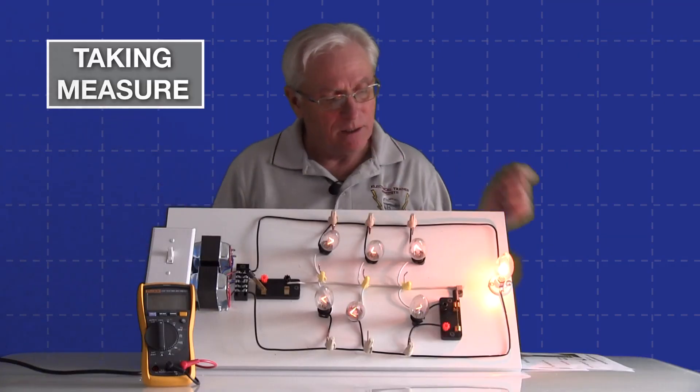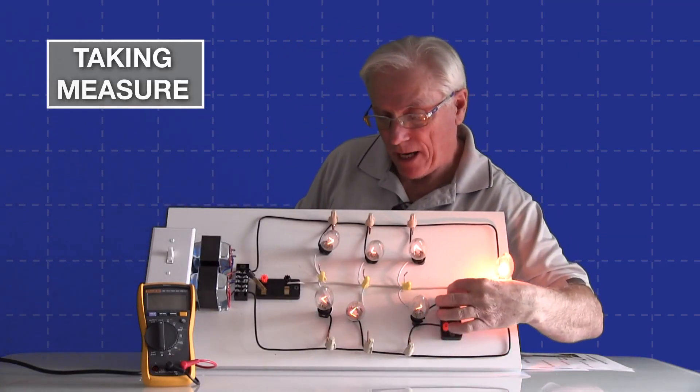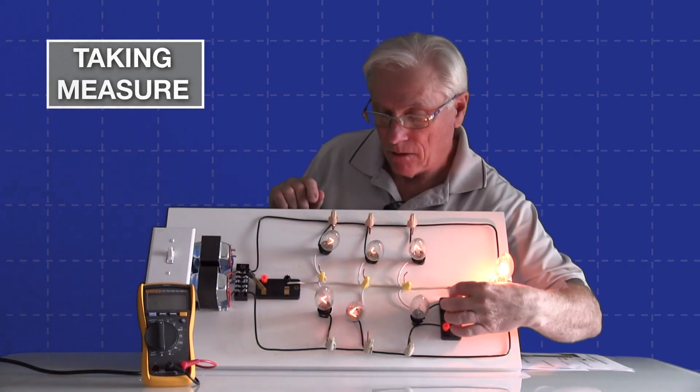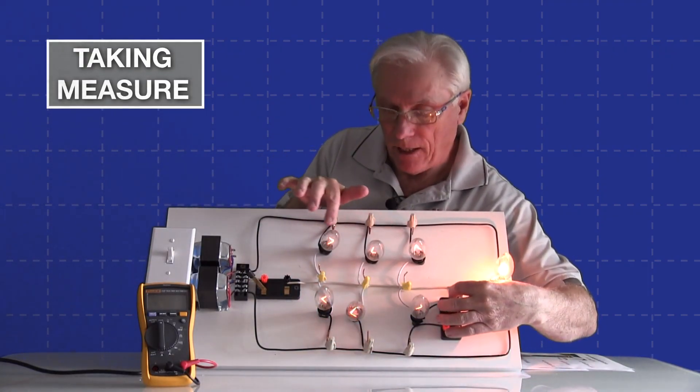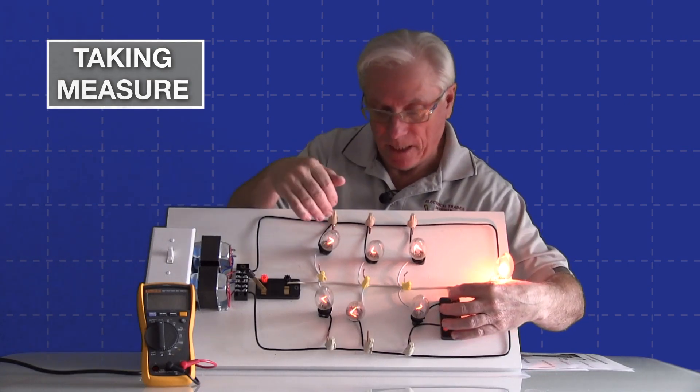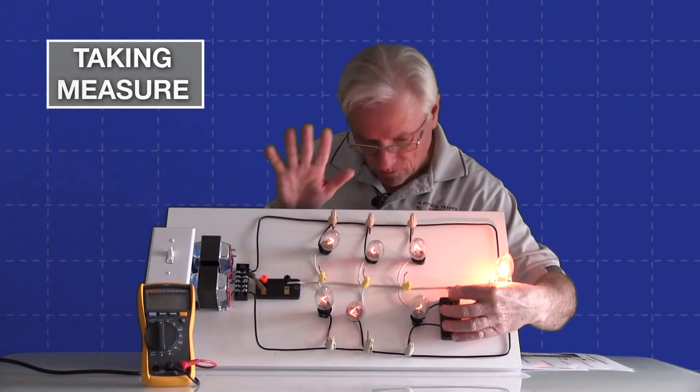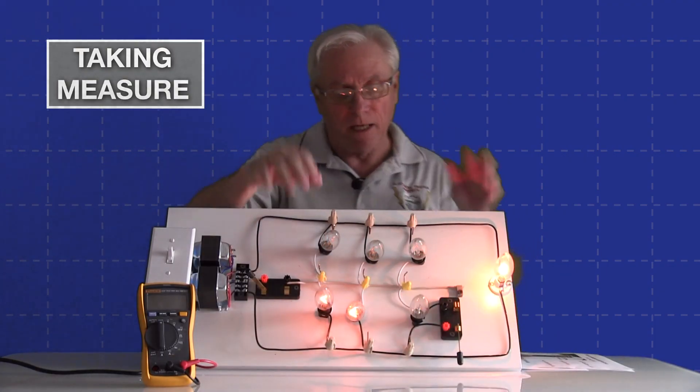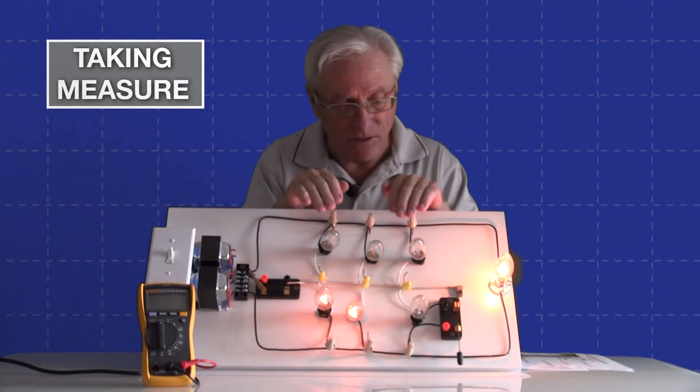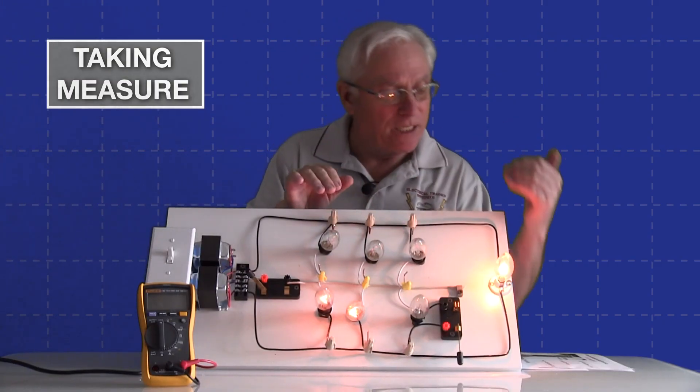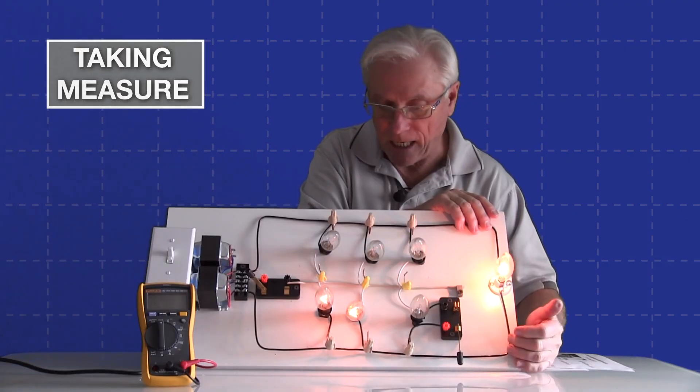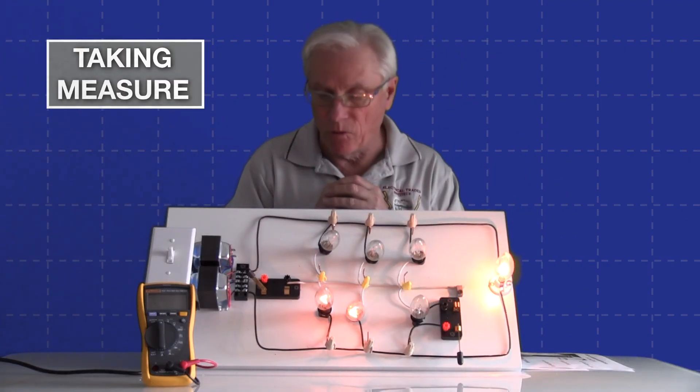But once that lamp is open we have a problem if I lose my neutral. The minute I open up this one lamp and drop it out, you can see what happened - these two got very bright and these got dim. The reason is we changed the voltage balance in what is essentially a series connection.